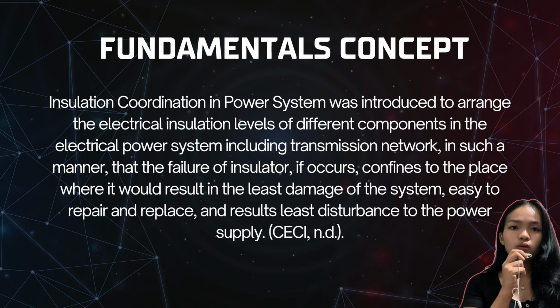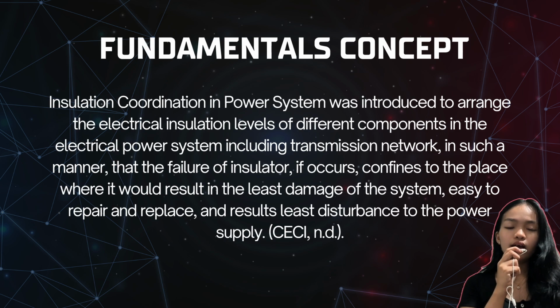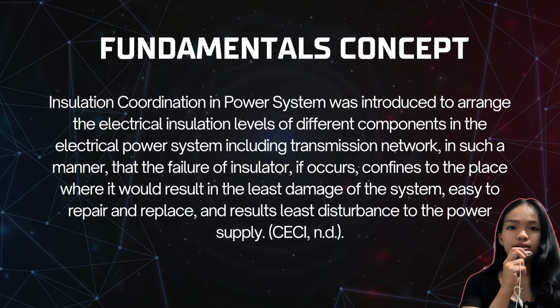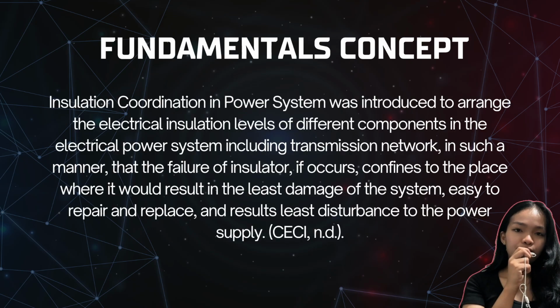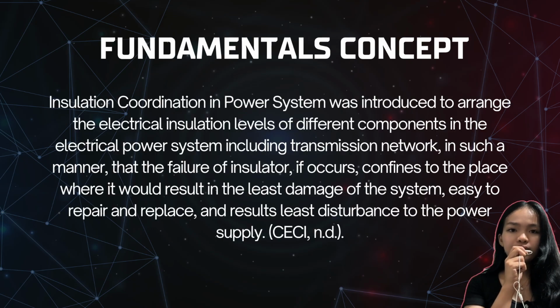The fundamental goal here is strategic arrangement. We want to set insulation levels across the system, including the transmission network. So, if an insulator failure does occur, it is confined to a specific area. By doing this, we can achieve three things. First, minimize system damage. Second, ensure parts are easy to repair or replace. Third, and most importantly, cause the least possible disturbance to the power supply.